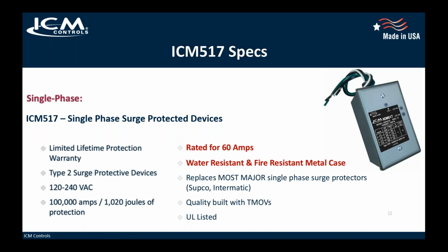This is what they call a Type 2. The 517 is a Type 2 surge protector, meaning it is meant to go on the load side of the line, on the load side of a disconnect, or on a circuit breaker rated for no more than 60 amps, from 20 to 60 amps. So what that means is this is not a whole house surge suppressor, and that's important to understand. Many people ask that question.